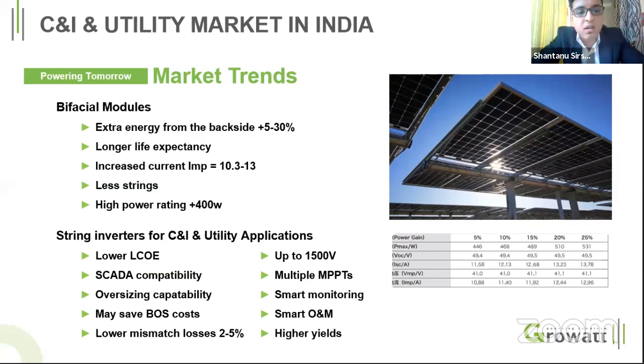The string inverters we use for C&I and utility applications should be compatible with the SCADA system. As discussed in the last panel regarding third-party data loggers, these should be easily compatible with any inverter brand, giving the end customer or EPC player flexibility in choosing any inverter brand as long as the communication protocol is open. For Growatt inverters, we provide an open Modbus protocol.